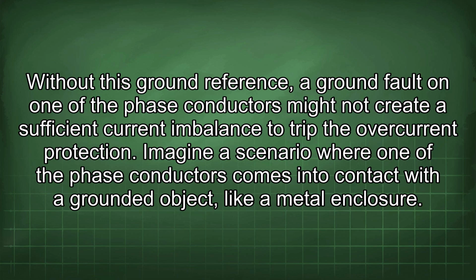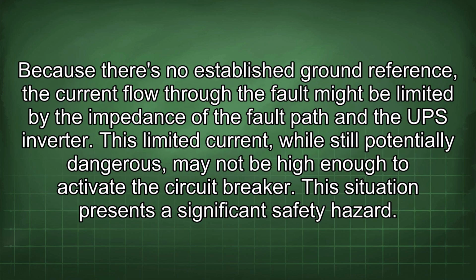Without this ground reference, a ground fault on one of the phase conductors might not create a sufficient current imbalance to trip the overcurrent protection. Imagine a scenario where one of the phase conductors comes into contact with a grounded object, like a metal enclosure. Because there's no established ground reference, the current flow through the fault might be limited by the impedance of the fault path and the UPS inverter. This limited current, while still potentially dangerous, may not be high enough to activate the circuit breaker.